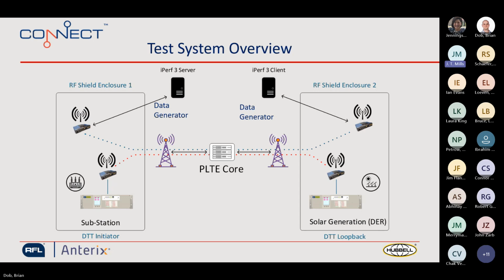So this is what we overall did for the test system overview. We took an RFL substation direct transfer trip device, the GARD 8000, and we put it in two different locations to simulate a field situation. On the left would be your utility substation, and on the right would be your solar generation plant, assuming those two devices are far enough apart that they're talking to two different towers, but connected in the back end to the core.